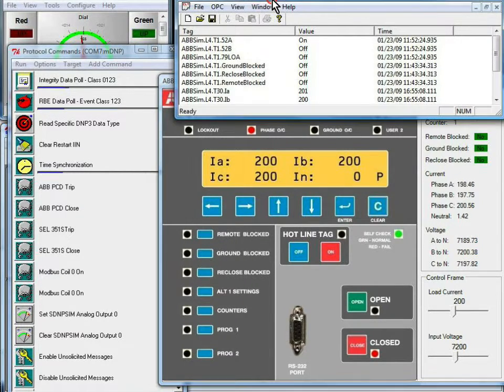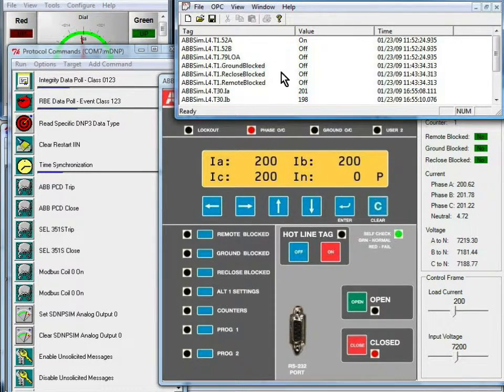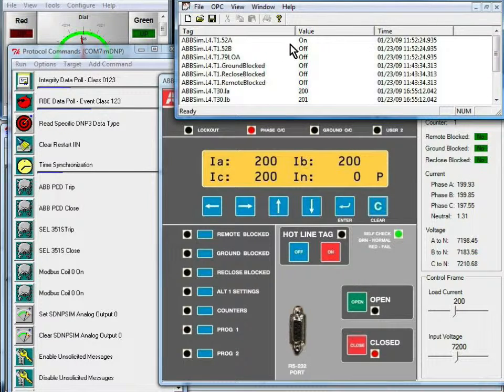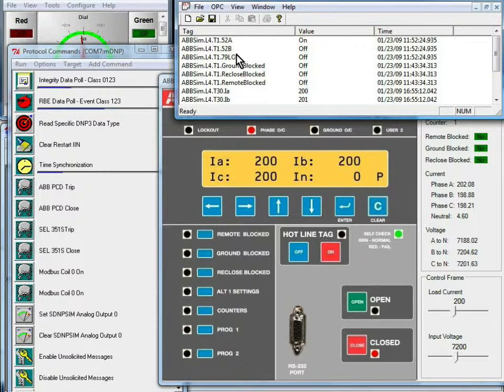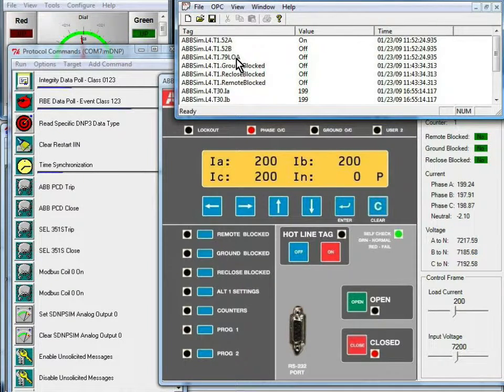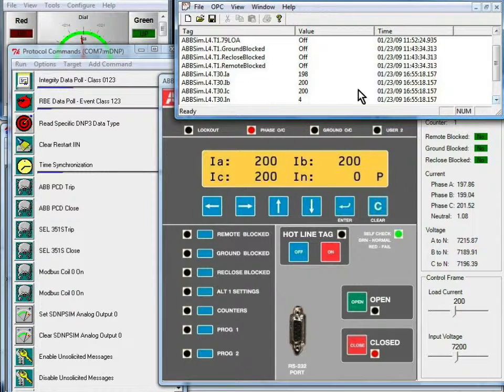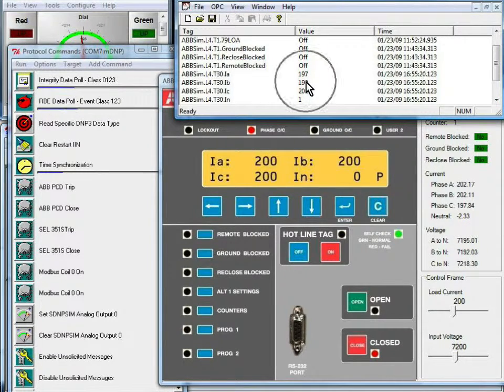If we look in the OPC client, we see the current state 52A is on and 52B and 79LOA are both off.